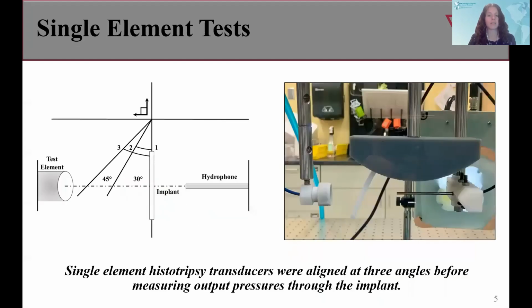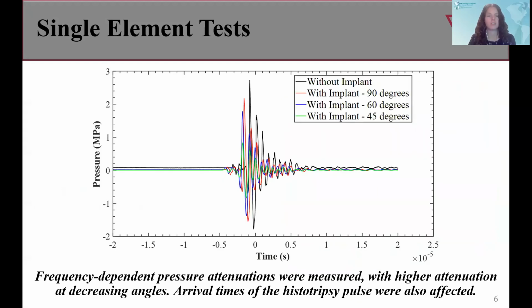To corroborate the findings in the Prada et al. study, 500 kilohertz, 1 megahertz, and 3 megahertz single-element histotripsy transducers were aligned at 3 angles relative to the implant: 90 degrees, 60 degrees, and 45 degrees. Then, a hydrophone was aligned to the focus of the single element and used to measure the output pressures with and without the placement of the implant in the field. The experimental setup for these experiments can be seen on the slide.